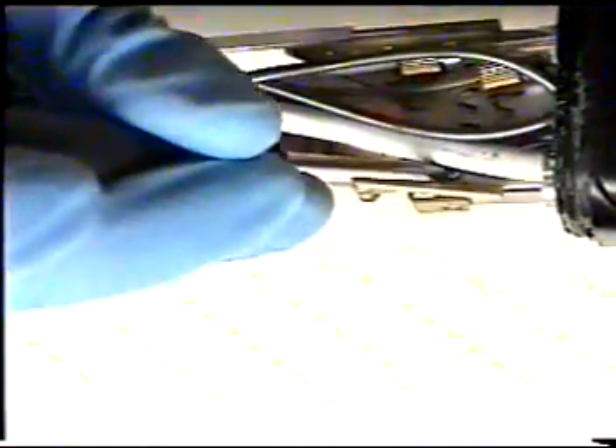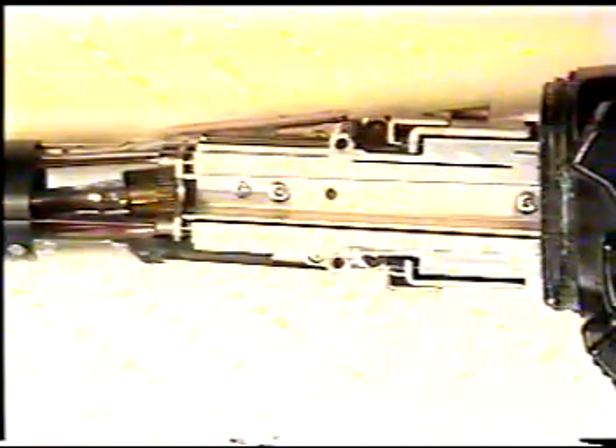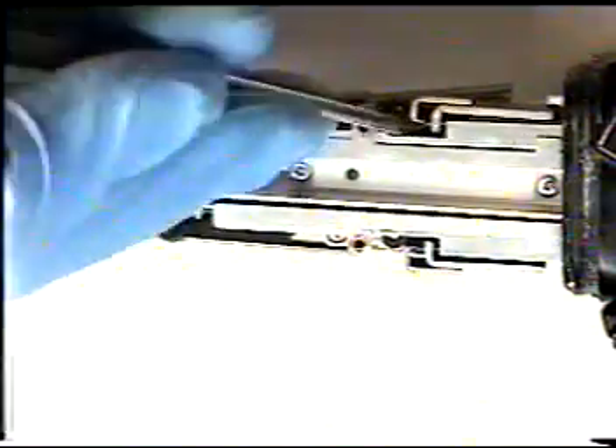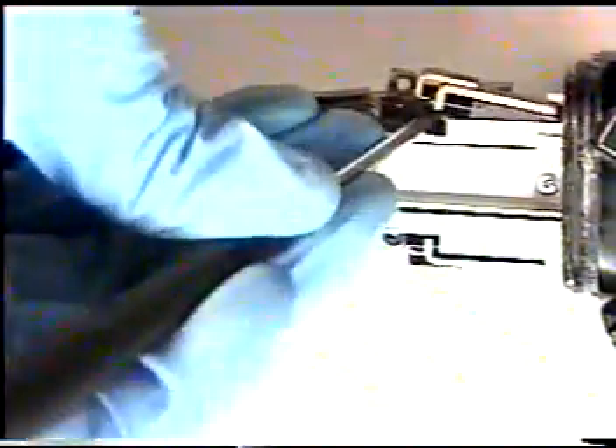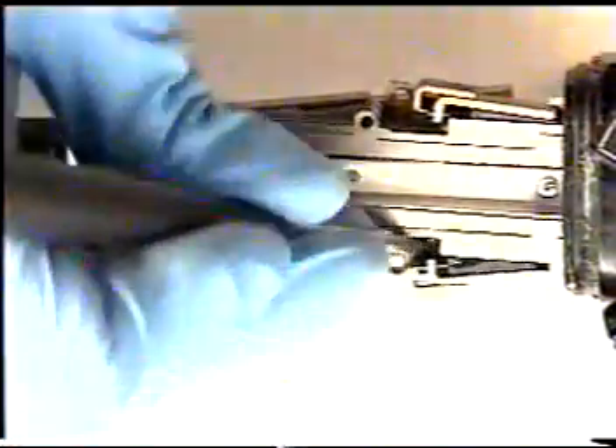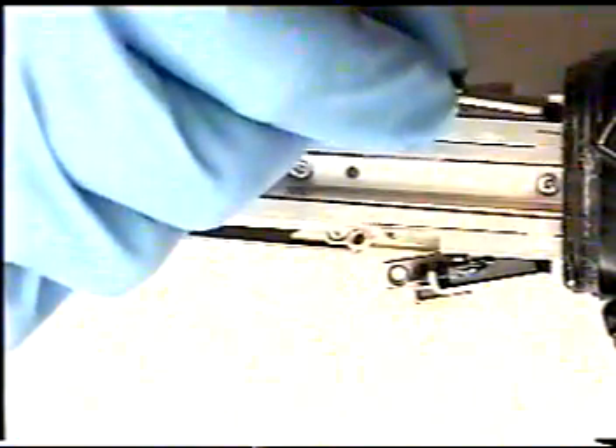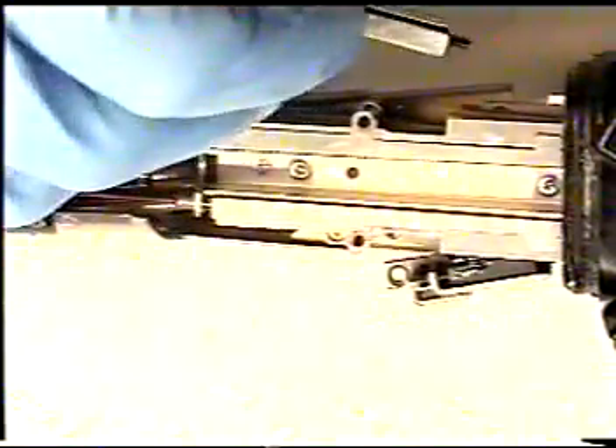Also on this side, it may be necessary to push very carefully aside the biopsy channel and remove that Phillips screw. Turn the instrument back over. Remove the angulation control blocks by prying them diagonally out and away from the body section to approximately a 45-degree angle. The angulation control blocks simply slide out.